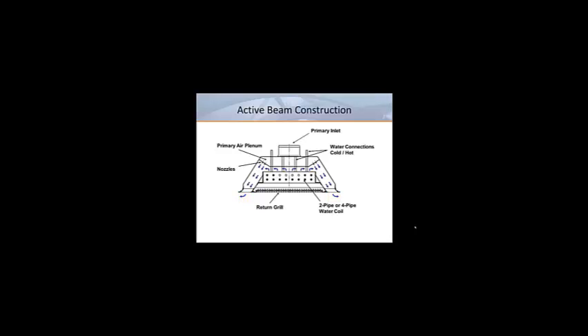Active beams take advantage of the same convective forces as passive beams but with a few big differences. Since active beams are supplied with air as well as water, they can provide much higher capacity through increased air motion. Active beams can also handle heating as well as cooling. Even more importantly, active beams address ventilation and latent loads.